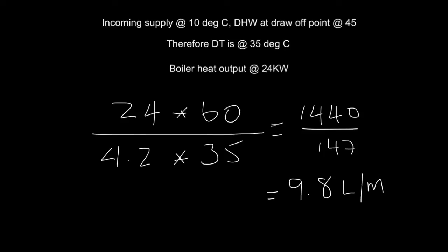What we'll do is look at various scenarios and find out how this information can come in useful in checking various points. Say, for instance, if we've got poor circulation through our heat exchanger, our plate heat exchanger, or maybe even poor circulation because the pump itself can't deliver as it should. It's simple enough to work out through the theory what the figures should be, and so determine or pinpoint where the fault might actually lie.